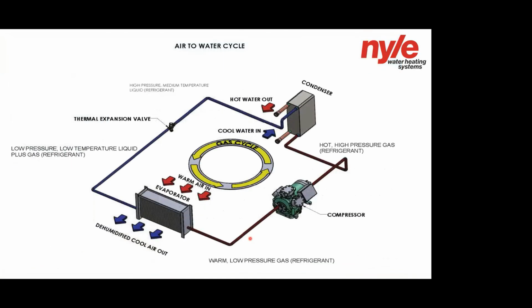So a lot of people talk about a refrigerant cycle. It can be confusing if you don't have any experience on the refrigerant side, like myself. Basically, we just have a compressor sending vapor, hot refrigerant into a heat exchanger. We use a lot of braze plates for this. That hot refrigerant is simply transferring its heat over to domestic water, where it goes to some storage tanks, and then it comes back as a high pressure liquid. At that point, we run it through a metering device and we drop it to low pressure, but still a liquid. And that liquid is looking for some heat to boil it back into a vapor.